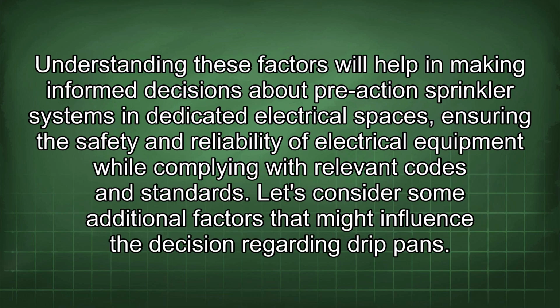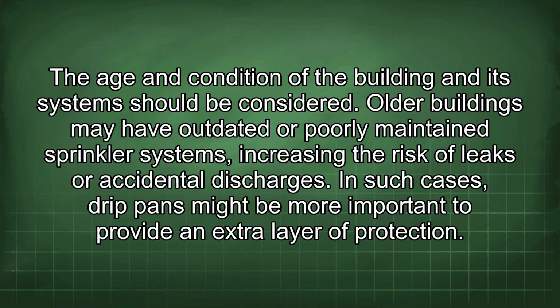Understanding these factors will help in making informed decisions about pre-action sprinkler systems in dedicated electrical spaces, ensuring the safety and reliability of electrical equipment while complying with relevant codes and standards. Let's consider some additional factors that might influence the decision regarding drip pans. The age and condition of the building and its systems should be considered. Older buildings may have outdated or poorly maintained sprinkler systems, increasing the risk of leaks or accidental discharges. In such cases, drip pans might be more important to provide an extra layer of protection.